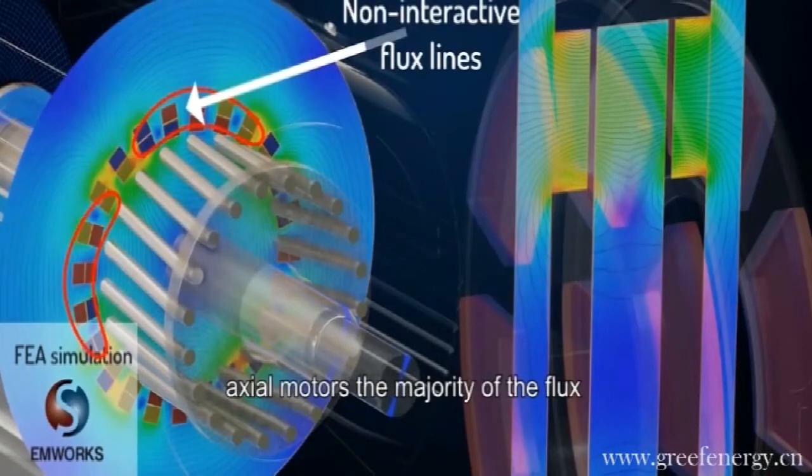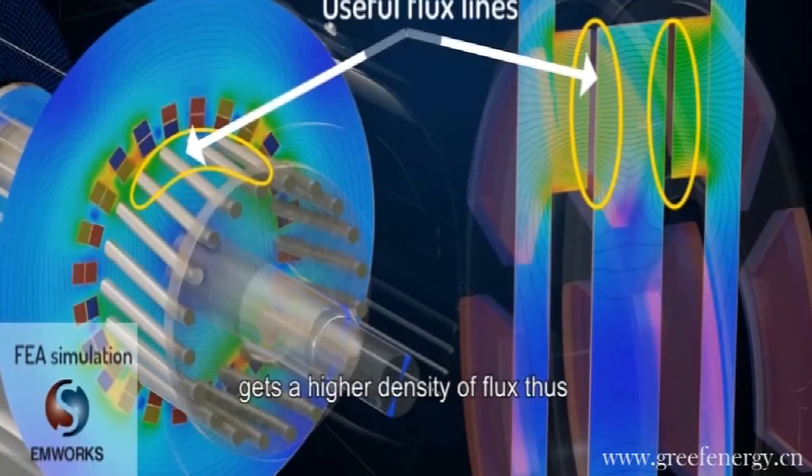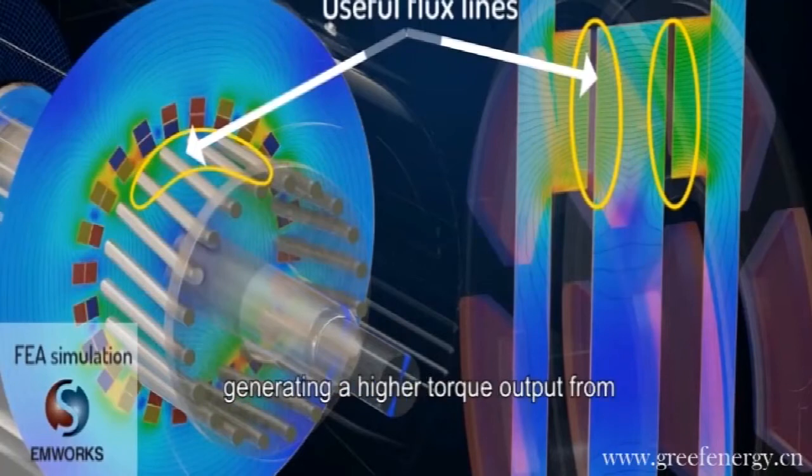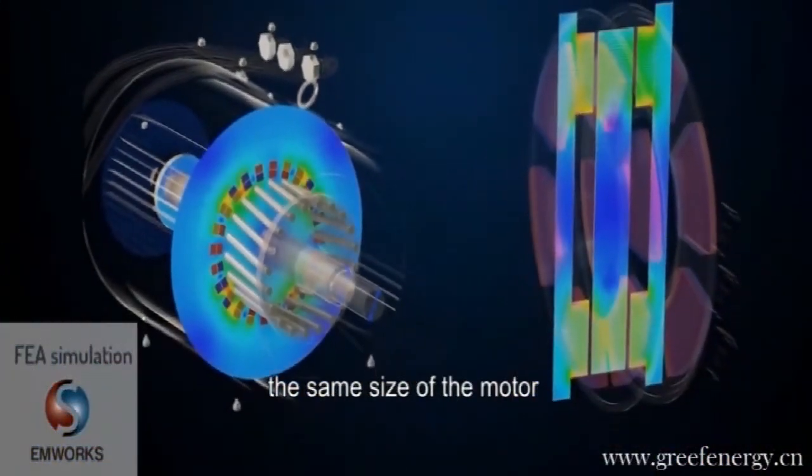On the other hand, in the axial motors, the majority of the flux lines lie in the useful work area to generate torque. For this reason, the axial flux motor gets a higher density of flux, thus generating a higher torque output from the same size of the motor.